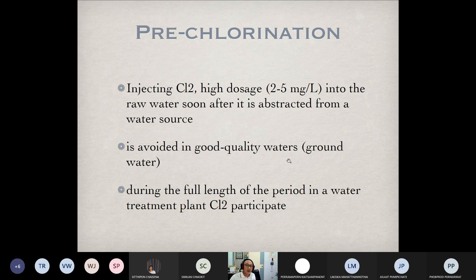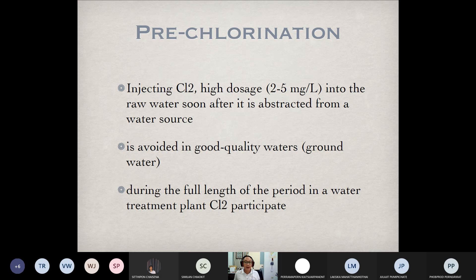For pre-chlorination, we normally inject chlorine at a high dosage of 2 to 5 milligrams per liter. Milligrams per liter is equivalent to ppm — parts per million.